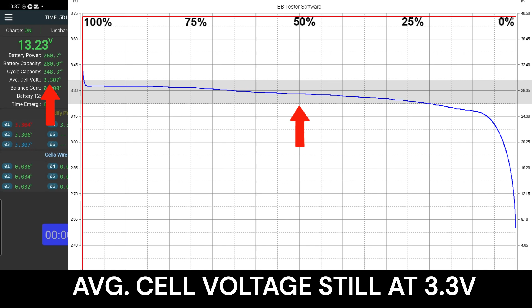When we were at 75% state of charge, it spiked to 100 amps. Yeah, there's a continuous draw, and that's greater than the last test, so let's stop this test and go to the next phase.